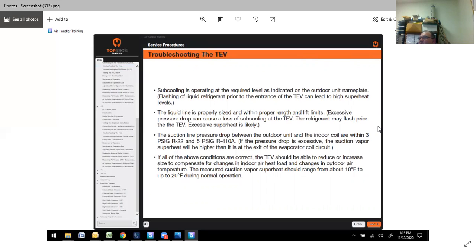Subcooling is operating at the required level as indicated on the outdoor unit nameplate. Flashing of the liquid refrigerant prior to the entrance of the TEV can lead to high superheat levels. Couple things to take into effect here. Verify your liquid line is properly sized and within proper length and line limits, lift limits. Excessive pressure drop can cause loss of subcooling at the TEV. The refrigerant may flash prior to the TEV. You could have excessive superheat that would be likely.